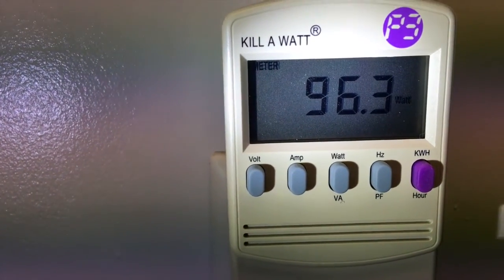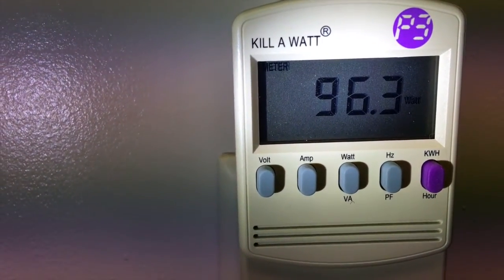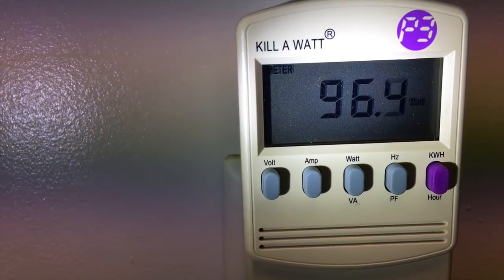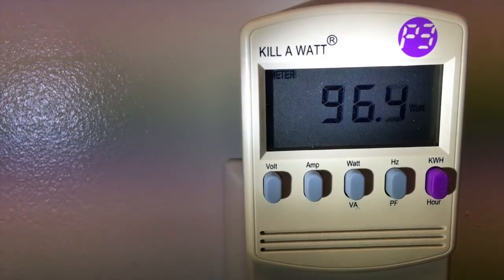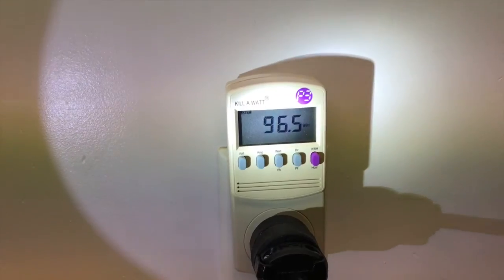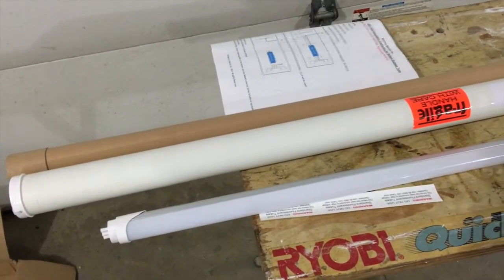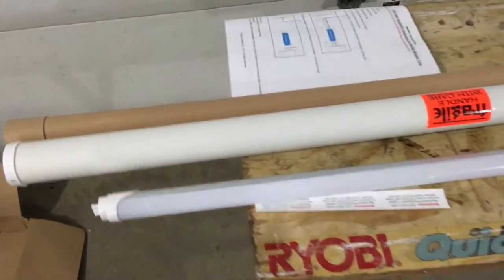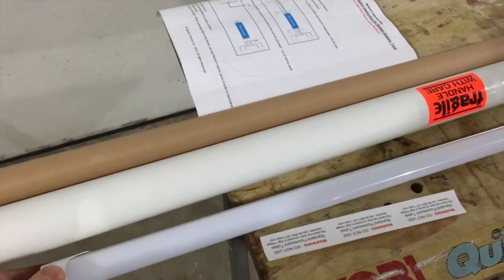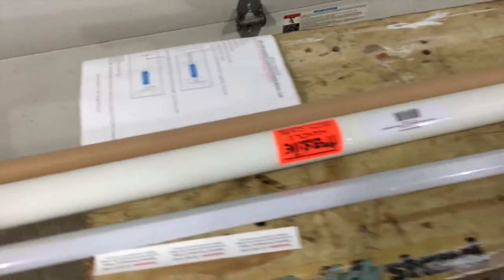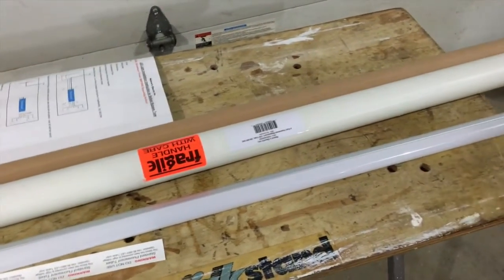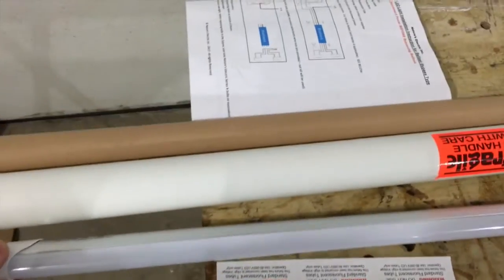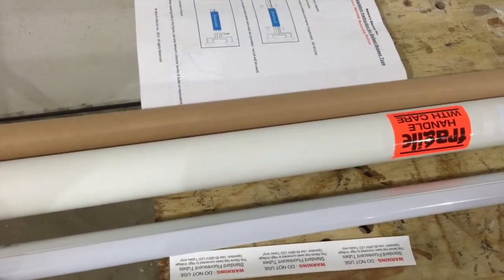So let's just round both of them up. We're using 97 watts here, we were using 38 over there. So you're talking approximately 60 watts different. For 60 watts additional power being used by these fluorescent lights and that ballast, we're really not getting any more brightness than we are with the LEDs. So there's our test. We used approximately just shy of 60 additional watts when we are with a fluorescent light with the four foot tubes compared to the LED. Again, the fluorescent was using ballast, this is not.